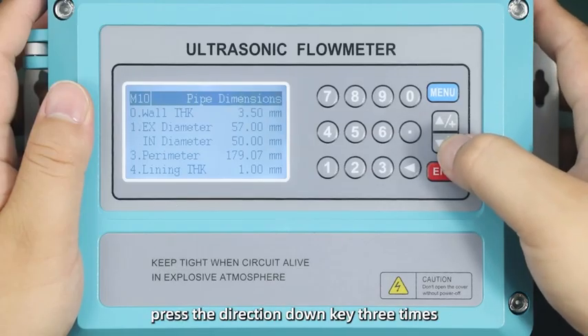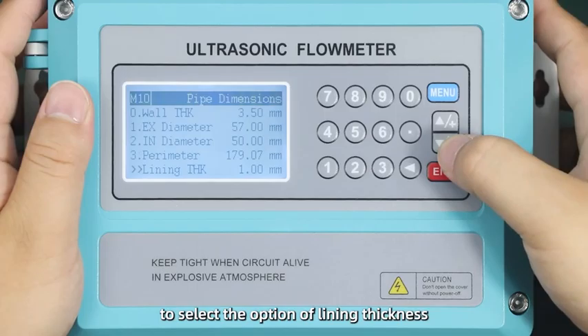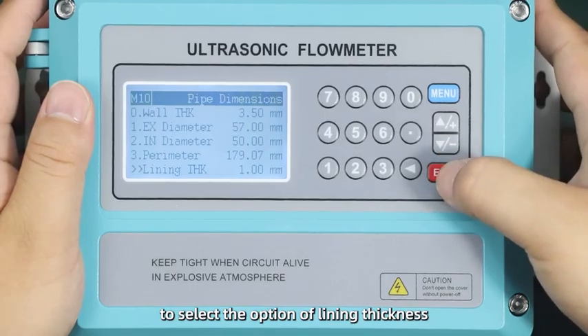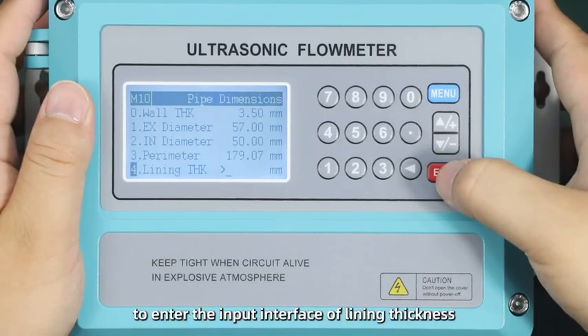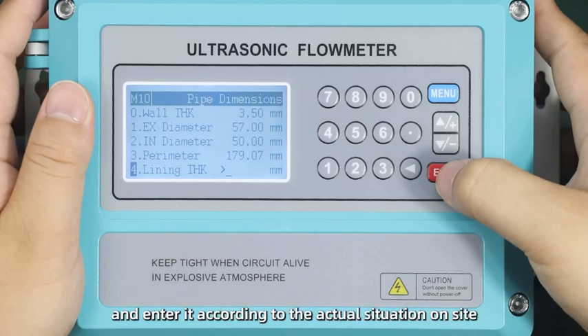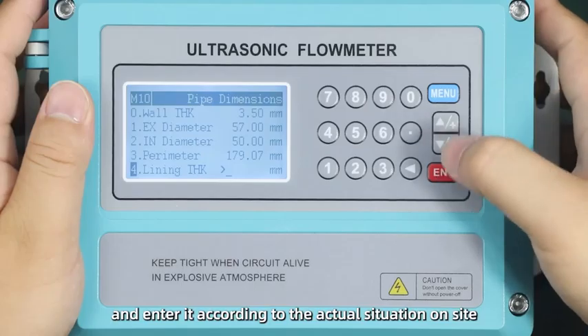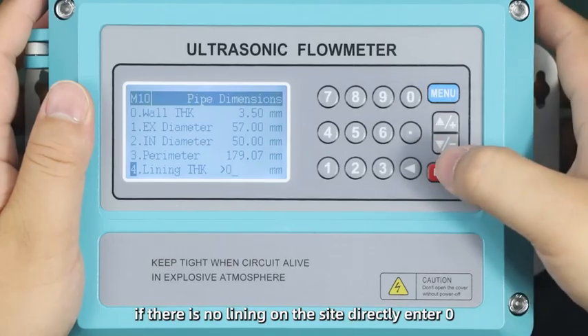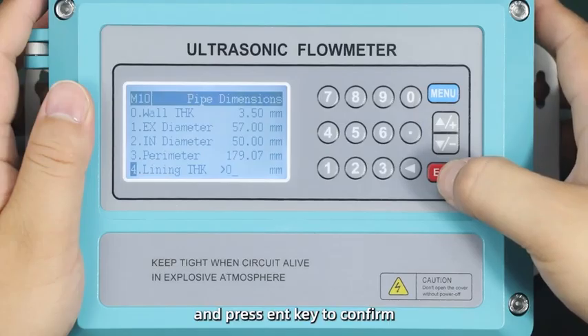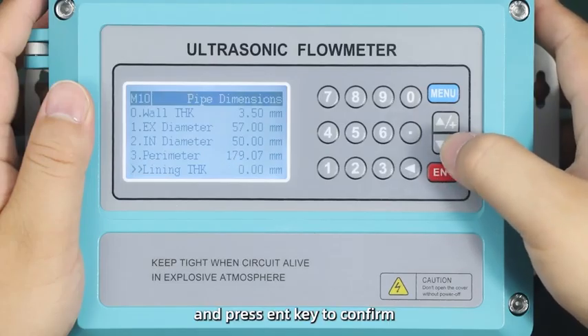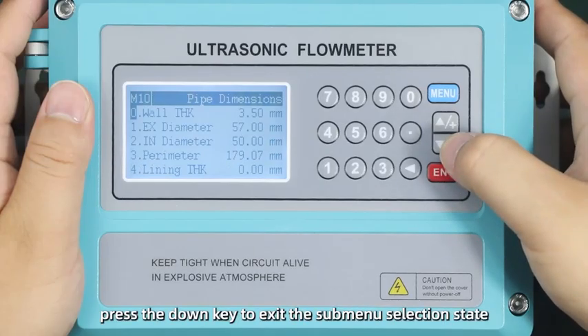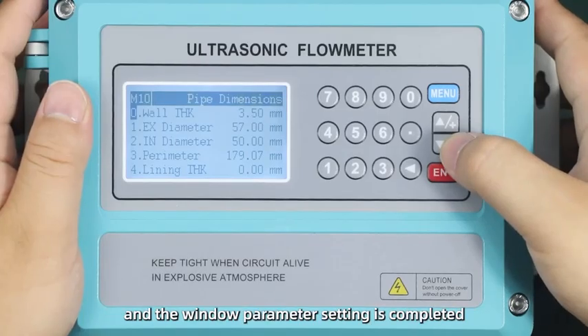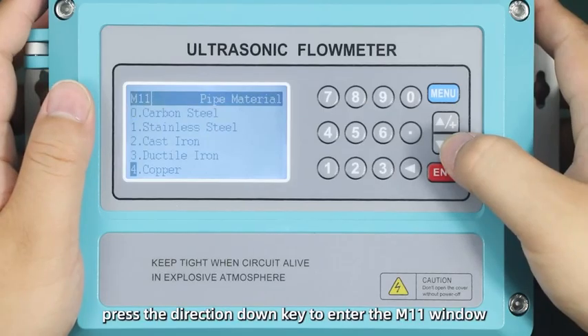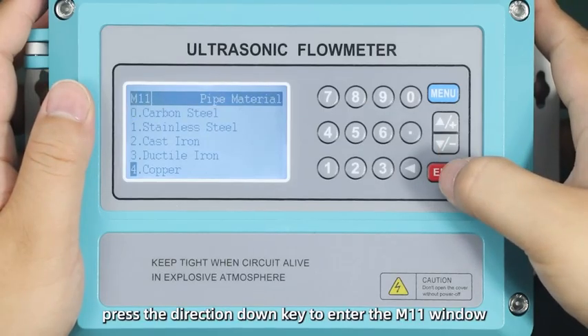Press the direction down key 3 times to select the option of lining thickness. Press ENT key to enter the input interface of lining thickness, and enter it according to the actual situation on site. If there is no lining on the site, directly enter 0, and press ENT key to confirm. Press the down key to exit the submenu selection state, and the window parameter setting is completed. Press the direction down key to enter the M11 window.